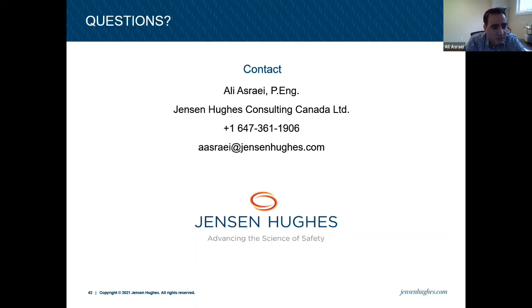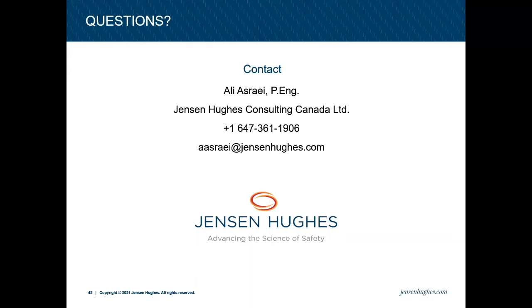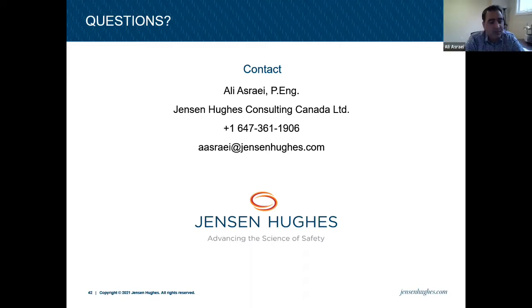So who would you recommend to do the smoke control test? Which trade? I don't know if we can do that or recommend anything. Do you want me to address that? Yeah. So you're commonly going to have consultants like Ali involved. You're going to have HVAC companies involved. But the fire code is silent on qualifications for smoke control testing. So for the maintenance, yes.